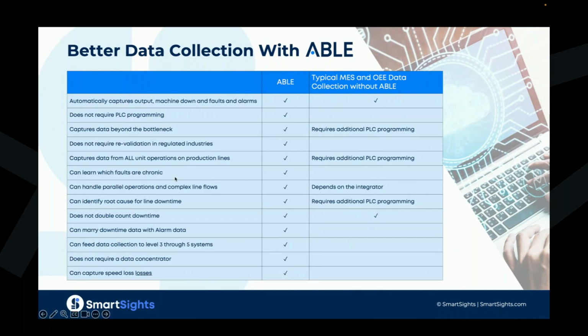Able has a concept called fault learning. What fault learning enables us to do is we don't have to go in, and a systems integrator doesn't have to configure every conceivable fault that might occur on a machine. Instead, we turn fault learning on, and with about 100 hours of production running time, we can usually discern about 90% of the chronic and repetitive faults that are occurring. Fault learning will report out on that, and those are the faults that the systems integrator will use to configure. However, with fault learning, if it stays on 6 months or 9 months down the road, and what was a one-off fault becomes a repetitive fault, fault learning will pick up on that, and it can be configured at that point in time.